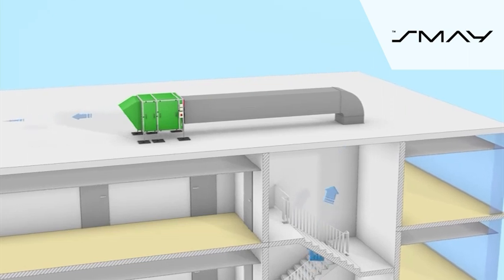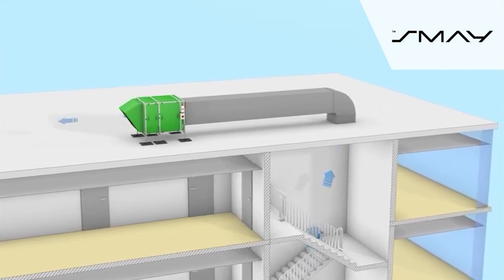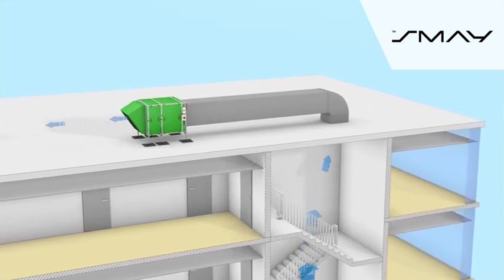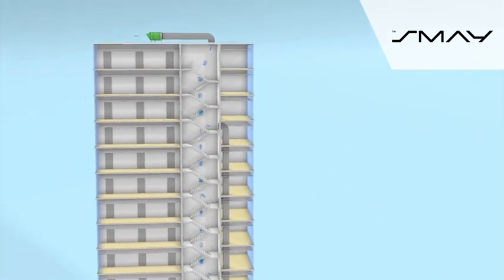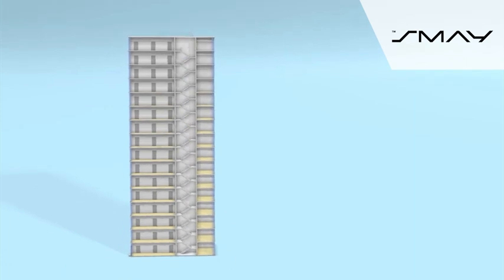The task of the second upper unit is to prevent the increase of overpressure in the upper part of the staircase, which may come into being as a result of the stack effect. This is a ductless pressurization system. No vertical air supply shaft is necessary.